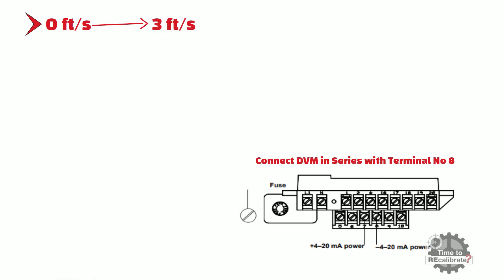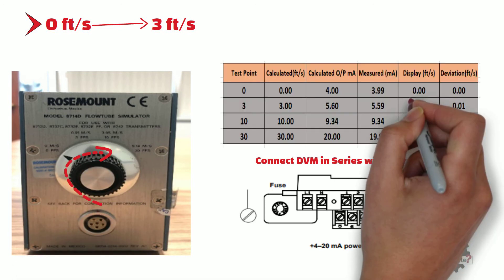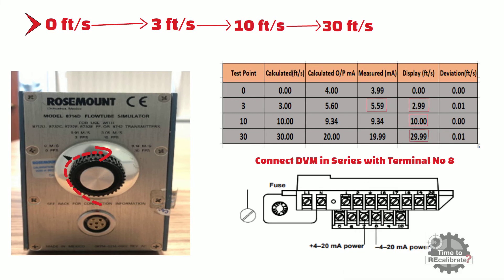Step 8: Move the knob of the simulator to the 3 feet per second position from 0 feet per second. The measured flow value will be displayed on the screen and should be close to 3 feet per second. Also note down the measured milliampere value from the digital voltmeter — this value should be close to 5.60mA. Now move the knob to 10 feet per second and note down the measured flow value, which should be close to 10 feet per second. Then move the knob to 30 feet per second — the measured flow should be close to 30 feet per second and the milliampere value should be close to 20mA.